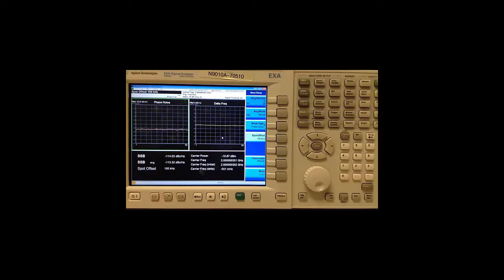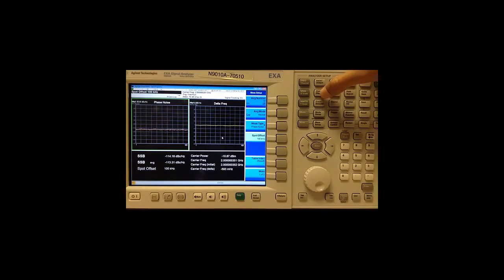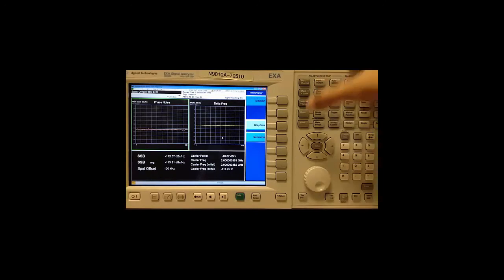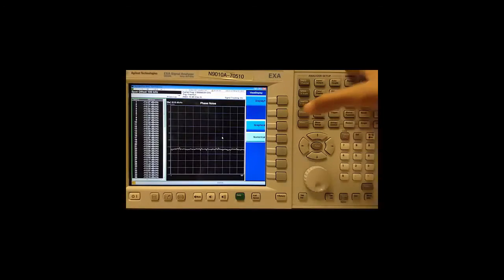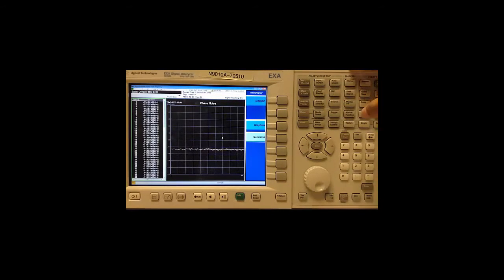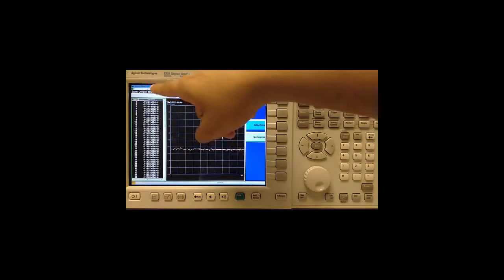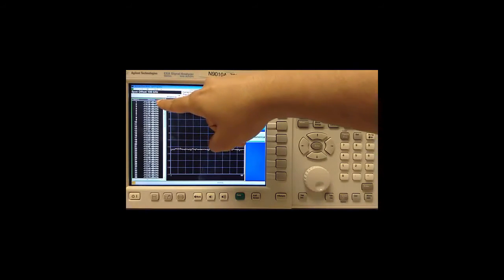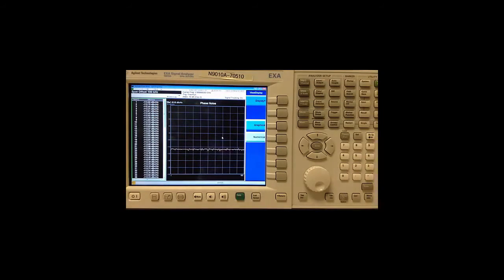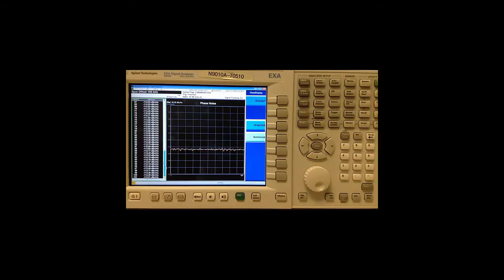We can change this to a tabular view under View Display and then Numerical. The phase noise trace is maintained and we now see additionally a table showing the last 101 spots and the phase noise measured at each of those spots.